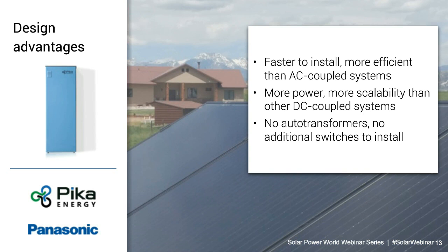So some design advantages of this system versus some other solar plus storage approaches. This is faster to install and more efficient than an AC coupled system. So you don't have 2 inverters. You've just got a single hybrid inverter. Batteries are integrated on the DC bus along with the PV. So the transmission efficiency is much better. There's not as many DC-AC conversions happening.